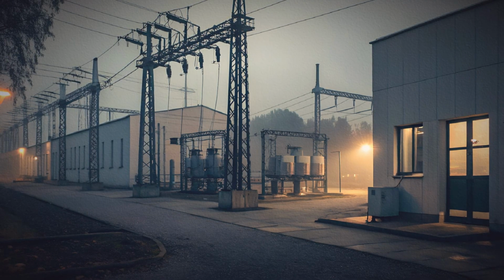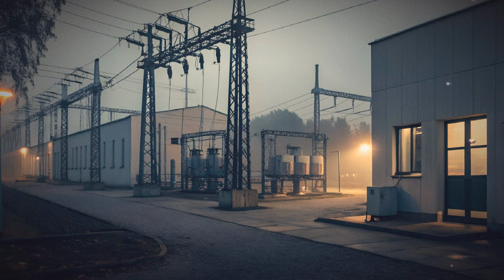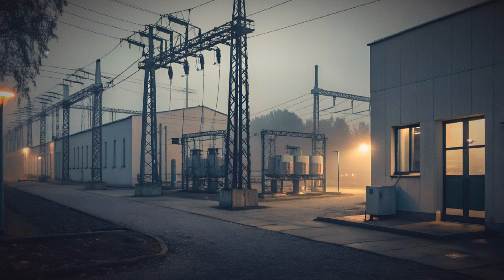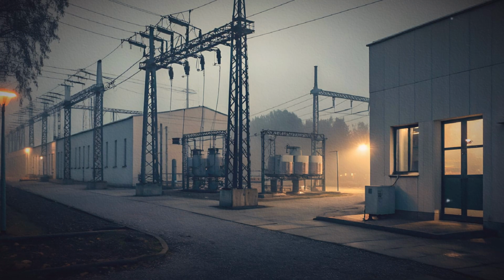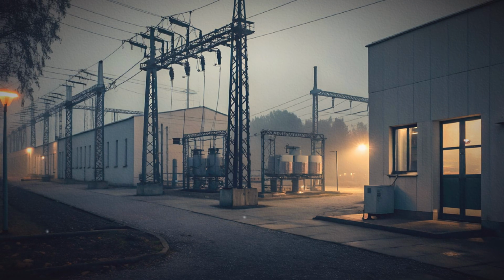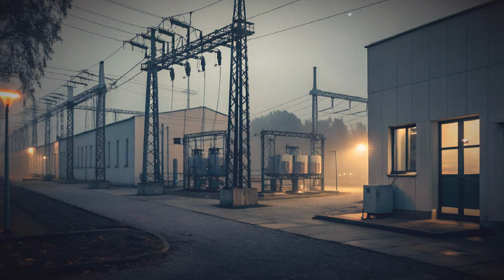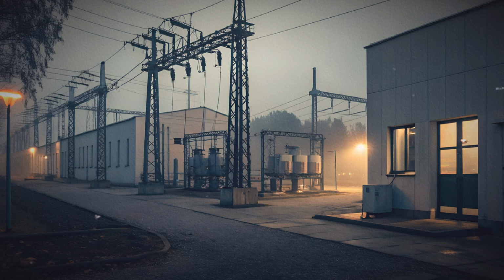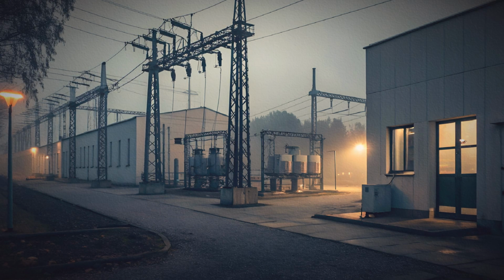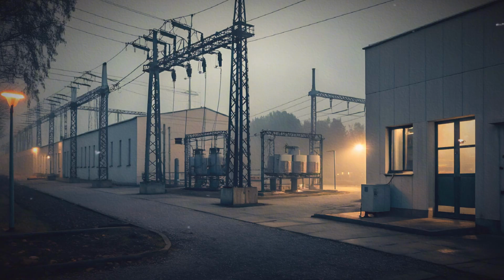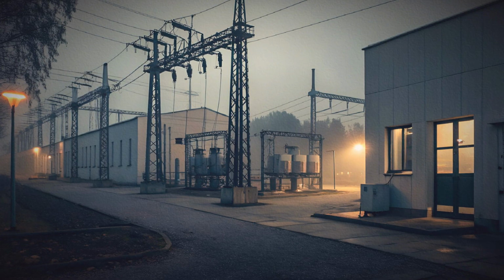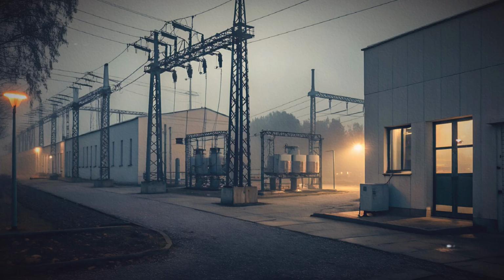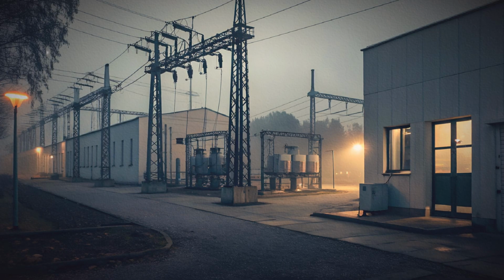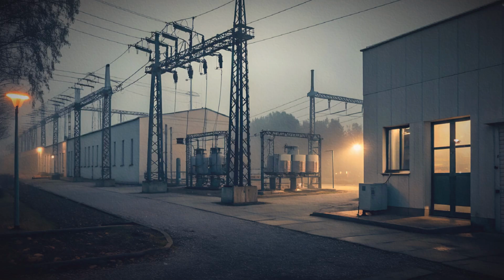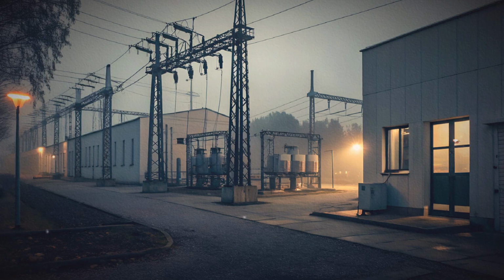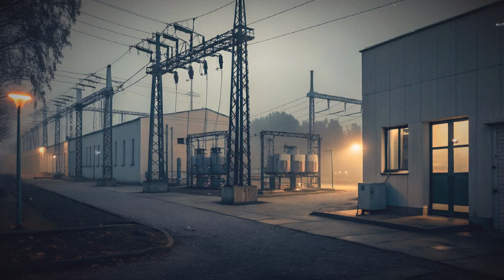Voltage regulation is a continuous activity within substations. Loads vary across hours, days, and seasons. These variations cause voltage at different points in the grid to change. Substations use several mechanisms to maintain voltage within required limits. On-load tap changers alter transformer winding ratios while the transformer remains energized. This allows small, discrete adjustments to the output voltage as load changes. Off-circuit tap changers are used when service can be interrupted for maintenance. Additional devices such as automatic voltage regulators provide more refined control when needed.